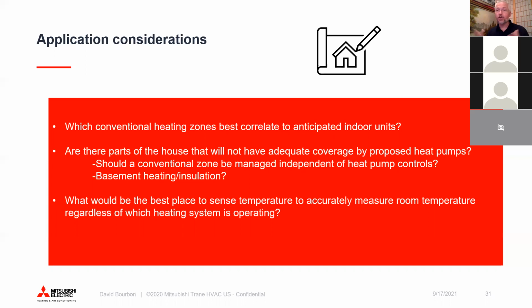Another, like a worst case scenario that we've seen in some circumstances, where somebody's like, well, I want the incentive for integrated controls, and this wouldn't really happen in New York, but like, oh, I'm going to put a heat pump up in my bedroom, and the integrated controls control the heat throughout the rest of the house. Well, that's not going to work so well. They may have only wanted the ductless in their bedroom, but it's inappropriate to connect that to the zones for the entire house, because when they adjust the temperature in the bedroom, that's not going to necessarily deliver heat to the rest of the house. So most of the season, it's just not going to work. And then when the bedroom's unable to keep up, it's not necessarily going to sense temperature appropriately for the rest of the house. So that's like a total disaster situation.